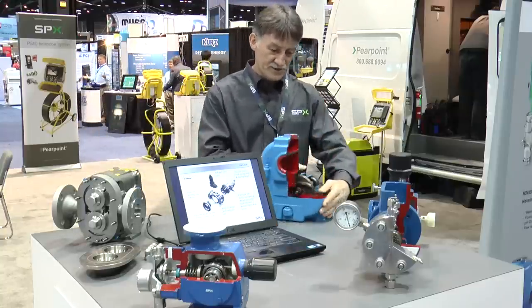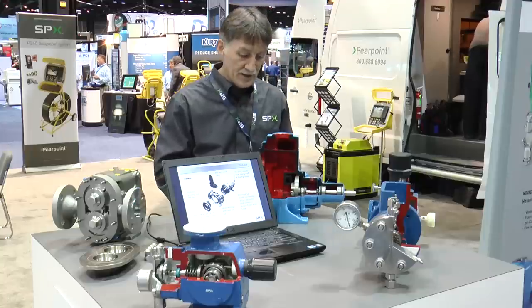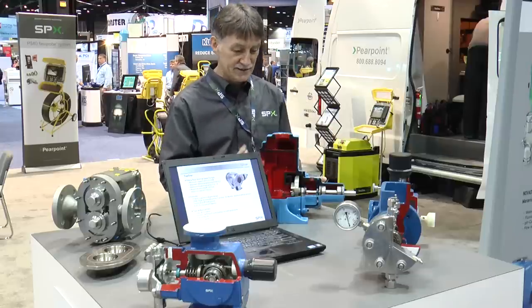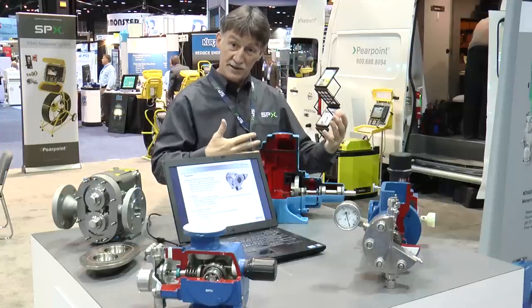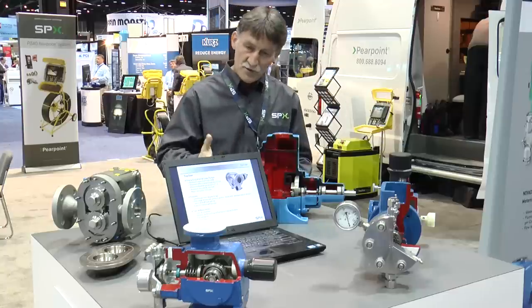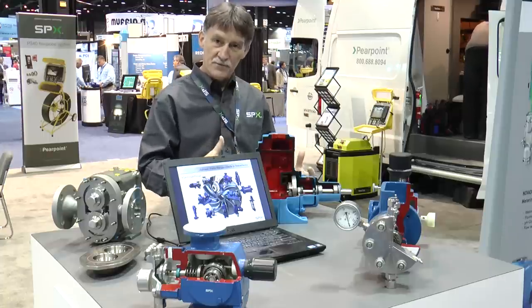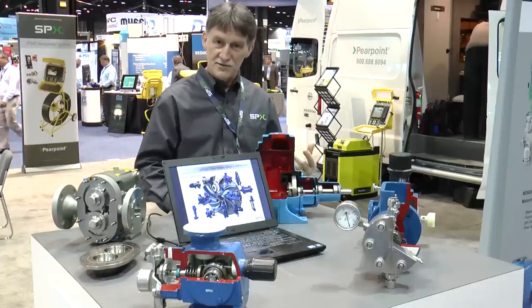And then for Johnson Pumps, today we feature our self-priming centrifugal pump. These are used for relatively clean liquids with small particulate and especially liquids with entrained gases. The way these pumps work, they will separate out the gases from the liquid so that you pump the gases out of the stream altogether. They keep the pump primed once it's got liquid in it, so you don't have to keep priming it every time you start the pump.